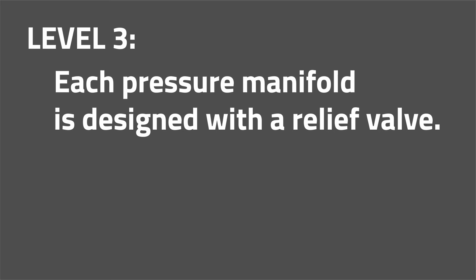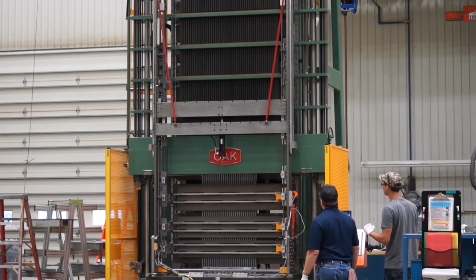On a conventional mechanical expander, the rods and tools have all been mechanically tied together. On the pressure expander machine, we've been able to actually separate the flaring tool from the belling tool. This enabled us to specifically design tooling for a belling OD and a flaring OD. The tooling can simply be changed out to increase the flaring diameter or to lower your bell depth. By the way, as we control the flare being added to the top of the tube, we can, by the turn of a knob, change the pressure that is applied onto the flare and make small adjustments on the fly to reduce splits.